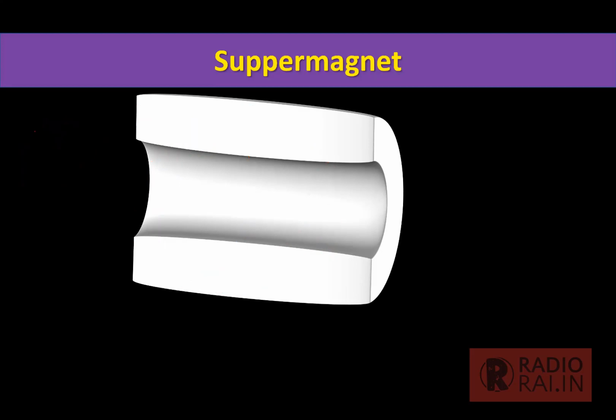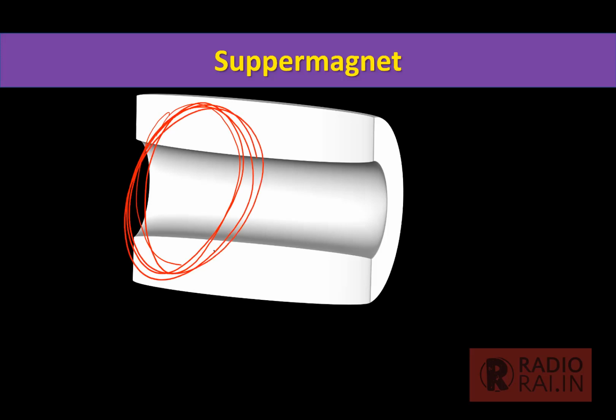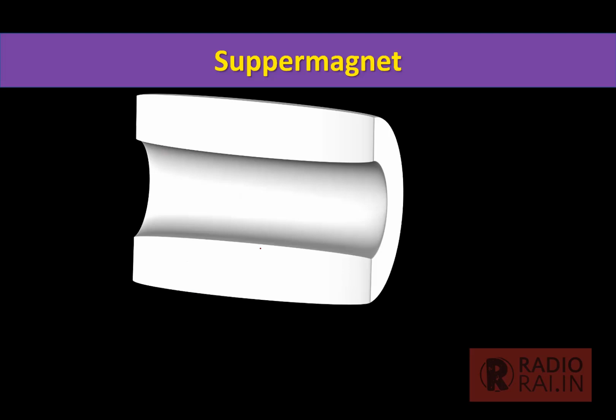So in a supermagnet, we activate the magnet by passing some current, and then we remove the external current and connect the wires. So a circuit is formed where there is a continuous flow of current, with no loss of current because there is no heat production. That is the supermagnet and the supermagnet type of MRI. Now how do I create this? By creating a niobium titanium alloy.